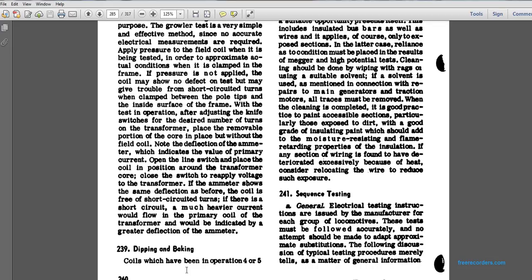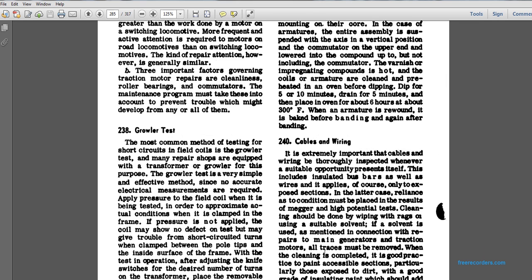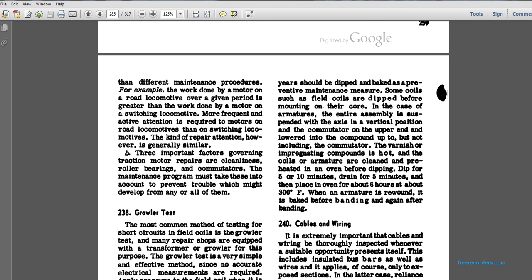239. Dipping and baking. Coils which have been in operation for 4 to 5 years should be dipped and baked as a preventive maintenance measure. Some coils, such as field coils, are dipped before mounting on their core. In this case, the armature's entire assembly is suspended in the axial vertical position, with the commutator on the upper end, and the lower end is dipped into the compound up to but not including the commutator.